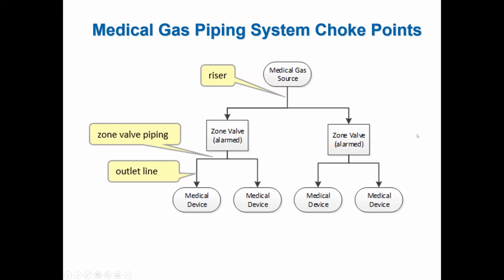These risers then spread out, and they supply zone valves. These are where your shutoff valves are, usually in the ICUs on the patient divisions. These are alarmed, and if the supply pressure drops, usually below 50 PSI, the alarm will go off. These zone valves represent a choke point because they can only handle so much flow before the alarm goes off. And finally, they spread out in outlet pipes going to individual rooms and individual medical devices.